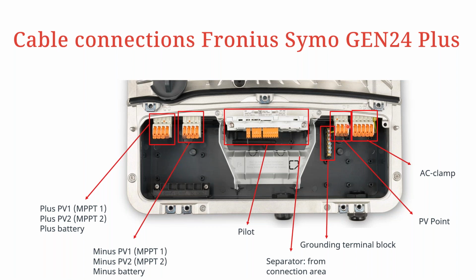And then we also have another separate connection for the PV point. And we have another additional connection, which is the grounding terminal block, that can be used to extend. Maybe if you want to connect to another node directly from the inverter, then you can connect to this one here. In the middle, we have the Pilot, which is the data communication unit or module of the GEN24 Plus. We also have the separator that keeps the data communication area separate from the DC connection area as well as the AC connection area. For the DC connection area, we have a shared connection between the PV and the batteries. In this case, we can see that, for instance, we do have the connection here for PV1.